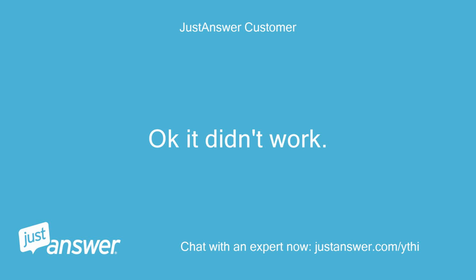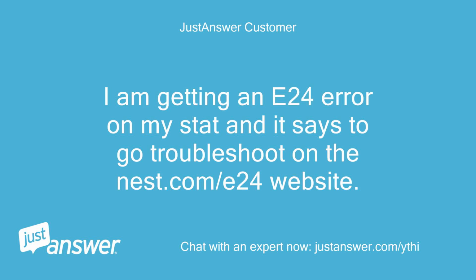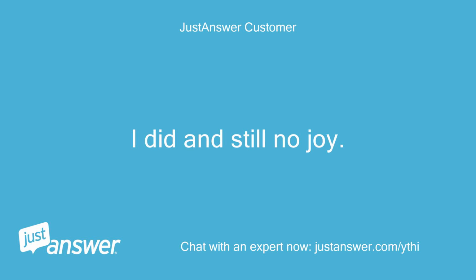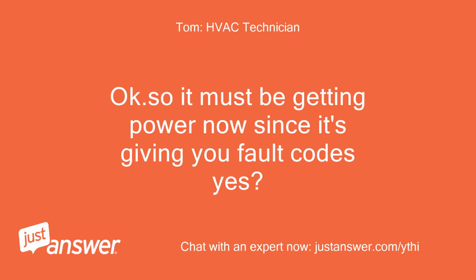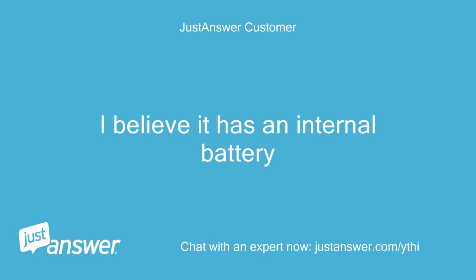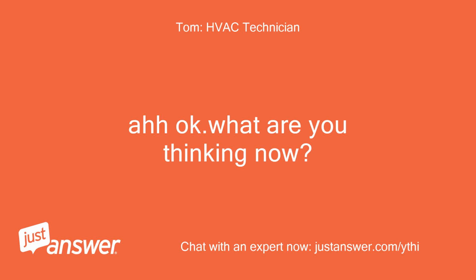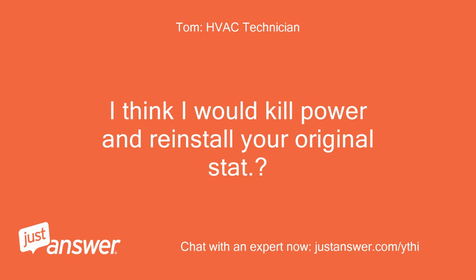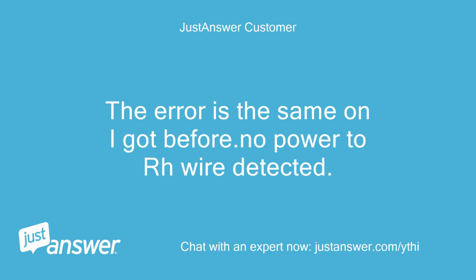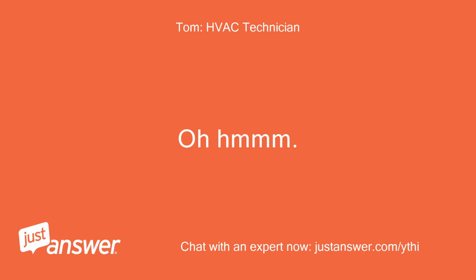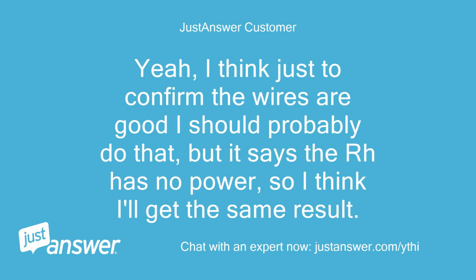Okay, it didn't work. I'm getting an E24 error on my stat and it says to go troubleshoot on the nest.com/E24 website. I did and still no joy. Okay. So it must be getting power now since it's giving you fault codes. Yes. I believe it has an internal battery. Okay. What are you thinking now? I think I would kill power and reinstall your original stat. The error is the same one I got before. No power to RH wire detected. Oh. Yeah, I think just to confirm the wires are good I should probably do that, but it says the RH has no power, so I think I'll get the same result.